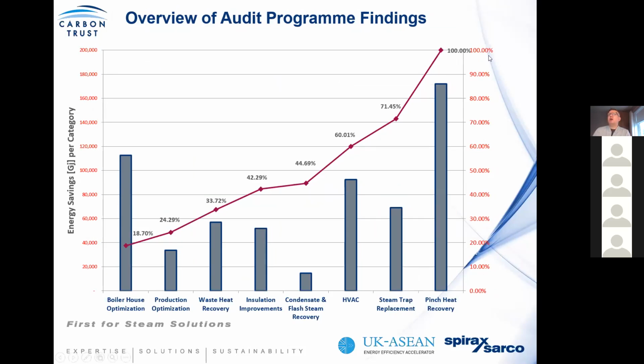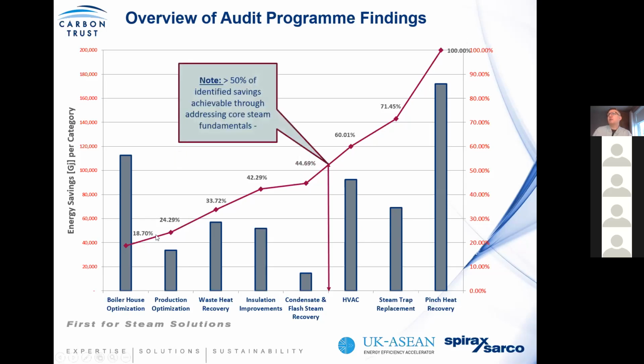So in other words, out of 100% of the energy that can be recovered, let's look at it in simplistic terms, without really looking at complex engineering, and it's important to recognize that efficiency in steam systems does not have to be complex. So what we have identified through analyzing this customer data is that over 50% of the identified savings can be easily achieved through core steam fundamentals, or addressing the inefficiencies in your steam system, without going to complex heat recovery solutions.